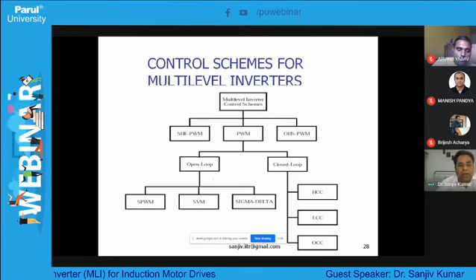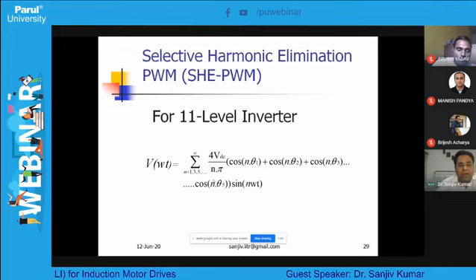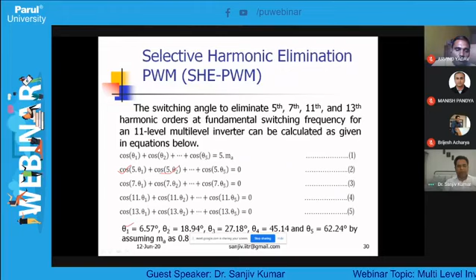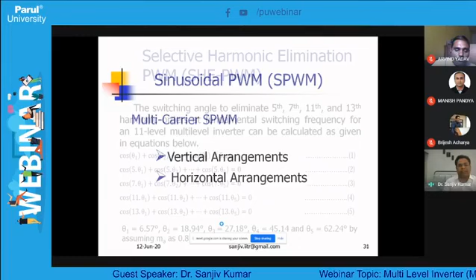But as far as MLI are concerned, my experience is that the selective harmonic elimination technique is very good for CHB type inverters, right? The beauty of this technique, you can see, for example, we want to eliminate 5, 7, 11, and 13, that is the 5th, 7th, 11th, and 13th order harmonics. We have to solve these equations, and we get the particular theta for various H-bridges. Depending upon these theta, it will eliminate all these harmonics. So, selectively, we especially want to eliminate whatsoever harmonics. We select the triggering of the devices in such a way that particular harmonics are eliminated.